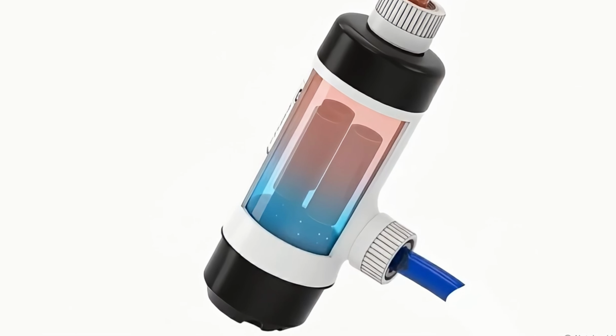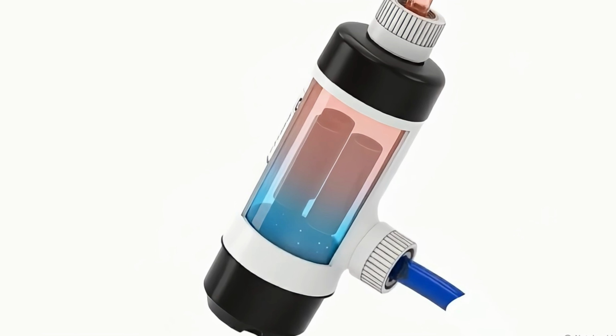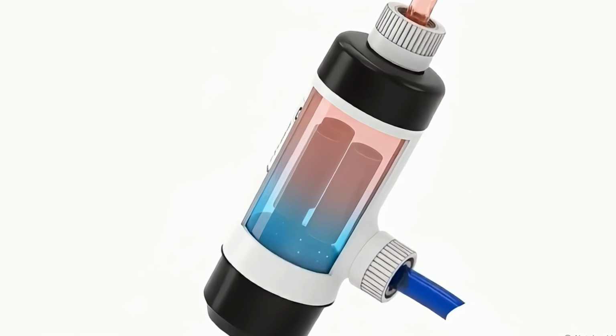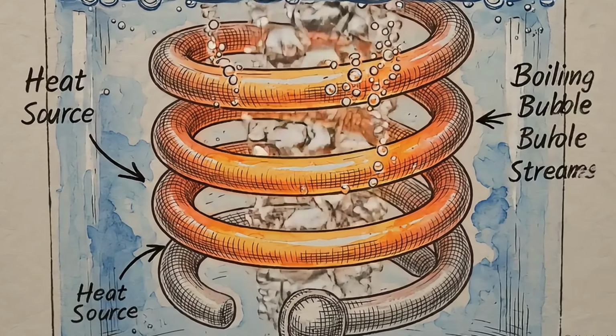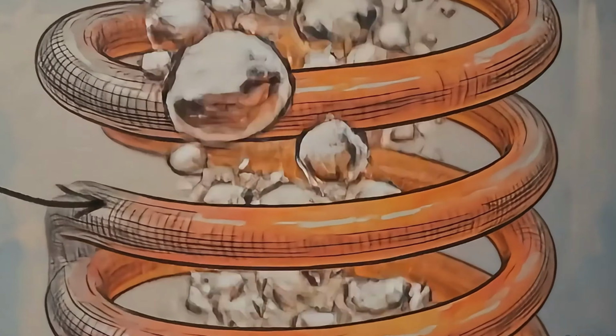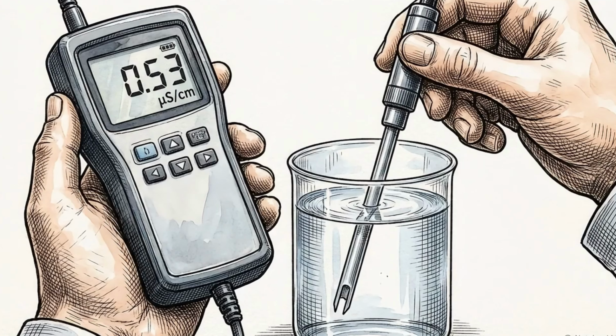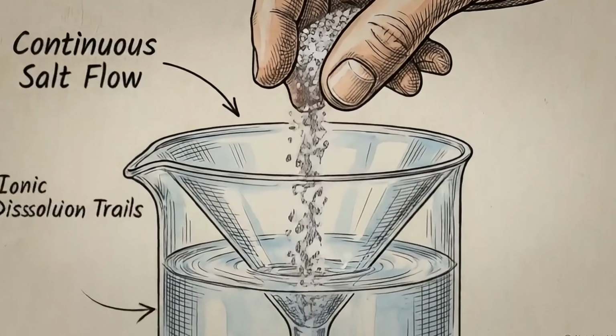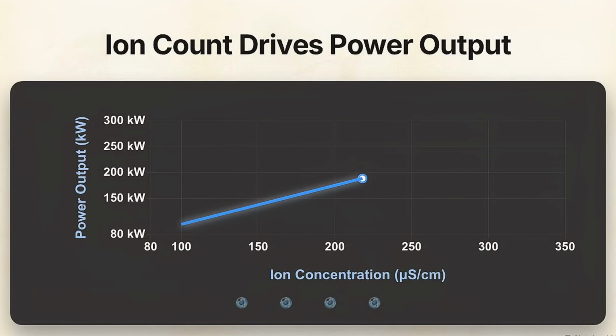Cold fluid constantly arrives at the bottom, acts as a resistor to generate heat, and exits the top at target temperature. There is no energy loss transferring heat from a glowing metal element through a protective casing and into a liquid. The fluid acts simultaneously as the electrical conductor, the precise resistor, and the final thermal output. Because the fluid dictates the power, the system's output can be manually calibrated. If a building is in an area with very soft water, an installer can literally add a pinch of table salt to the system to increase the ion count, lower the resistance, and boost the heating power. If the local water is too hard, they dilute it with distilled water to bring the power draw back down.